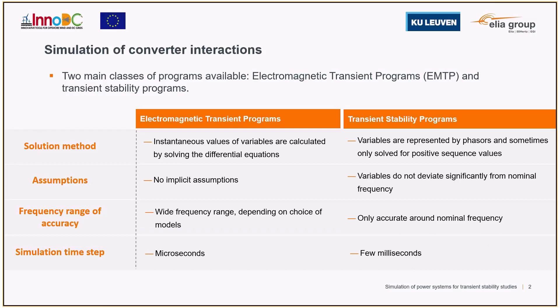Models in EMTP do not necessarily have any implicit assumptions and can be quite detailed, leading to a more accurate representation of the system over a wide frequency range. On the other hand, in transient stability programs it is assumed that oscillations are restricted to the low frequency spectrum, allowing for more simplified models but also restricting the frequency range of accuracy.